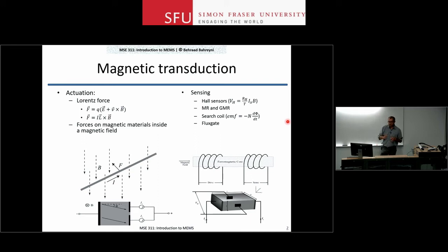And one of the properties of ferromagnetic cores is that they saturate very quickly, right? So the BH curve for ferromagnetic materials has some saturation. What they do here is pass a current through the first coil, this drive coil, that is so large that it pushes the ferromagnetic core to its saturation limit. Once you are near that saturation limit, because of the nonlinearity in the B and H relationship, the second coil that is picking up the magnetic field from the core is going to produce higher harmonics of the drive signal. So if you're driving it, let's say, at 1 kilohertz, you will see the 1 kilohertz plus the 2 kilohertz signal and so on and so forth. Particularly the second harmonic is important here.